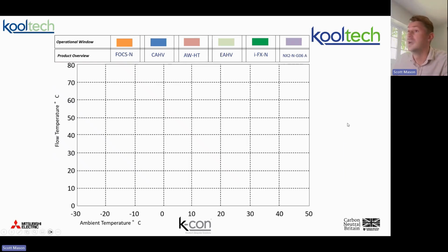What you have on the screen now is quite a cool chart, and this is a bunch of our popular products along the top of the screen. So the CAHV, this is like our sort of mainstream market leading unit. This is the Mitsubishi CAHV unit. Generally 40 kilowatts, but the kilowatt rating does drop off at lower ambients slightly. So when you get down towards -5, you're sort of closer to maybe 35 kilowatts rather than 40. But at 0, you're closer to 40 rather than 35. So the output is affected. Anything above 2-3 degrees is almost a constant 40 kilowatts for this unit.